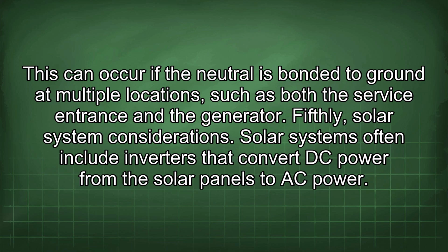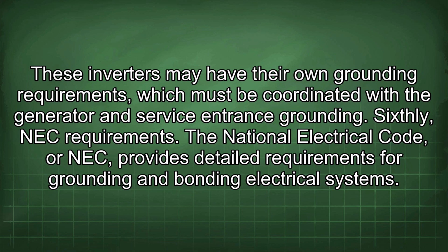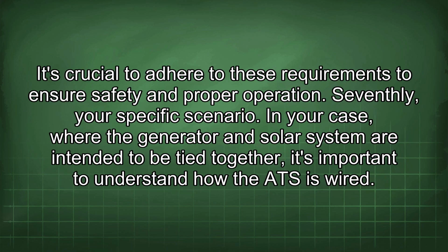Solar systems often include inverters that convert DC power from the solar panels to AC power. These inverters may have their own grounding requirements, which must be coordinated with the generator and service entrance grounding. Sixthly, NEC requirements. The National Electrical Code, or NEC, provides detailed requirements for grounding and bonding electrical systems. It's crucial to adhere to these requirements to ensure safety and proper operation.